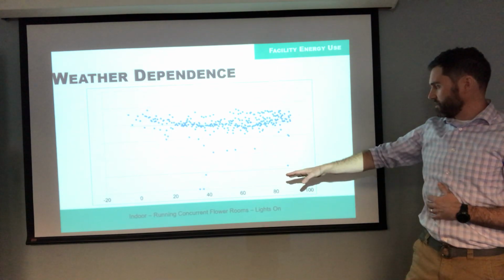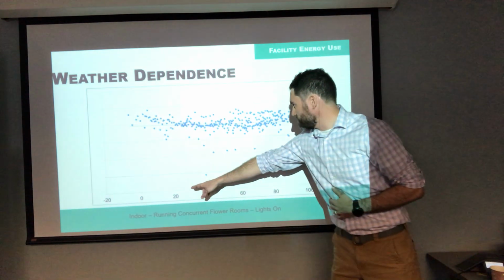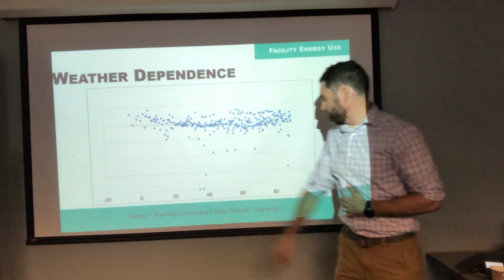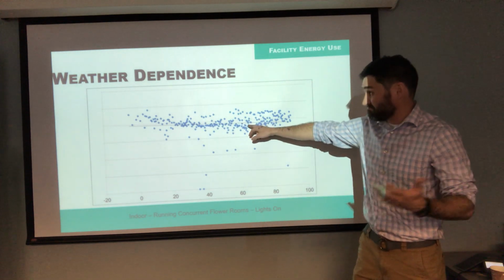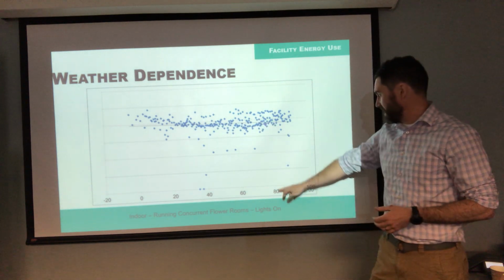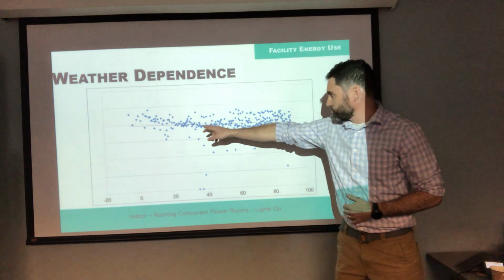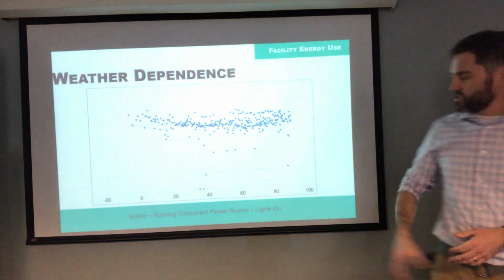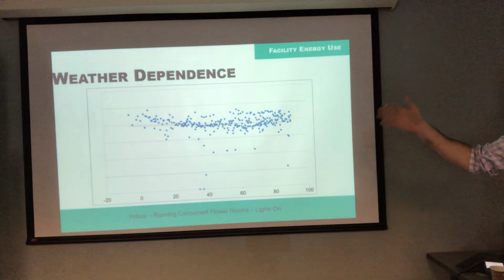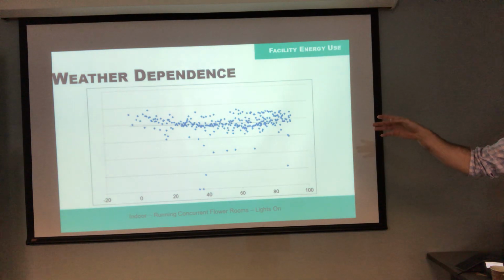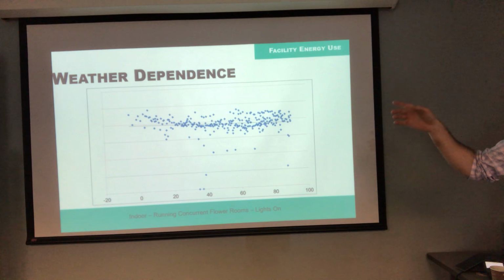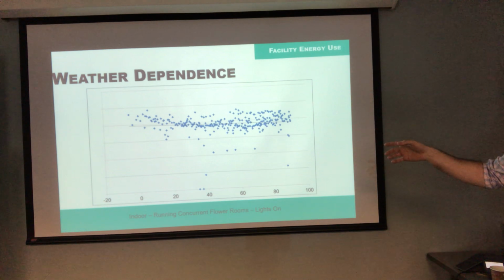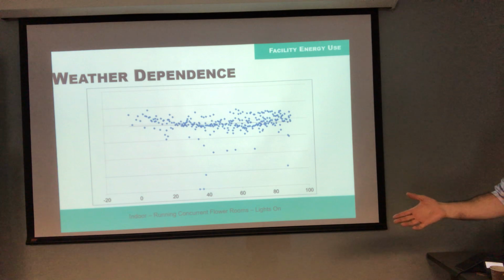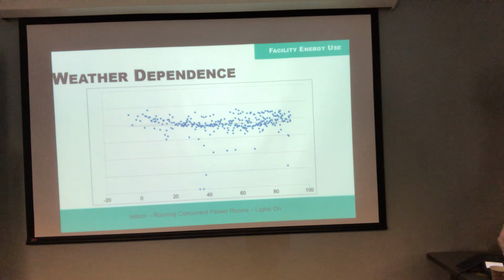You can see this thin black line, that's the trend line of this data. At 20 degrees I'm using about that much kW. At 60 degrees, about the same. At 80 degrees, about the same. My trend line is super flat, so this is weather independent. The amount of energy this facility uses when the lights are on is completely dominated by the internal loads, and those loads are the lights and the equipment that has to process those loads.